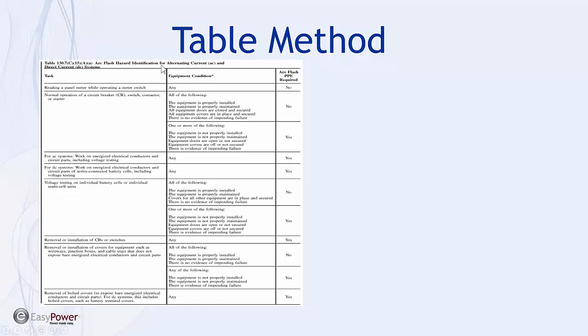When we talk about the table method in 2015 for determining PPE required for arc flash safety, the descriptions start with a series of tables that give a go/no-go on whether PPE is required. As you get into more detail where it is required, they give a series of questions on how to determine that. This is significant because, at least in this first category, they tell us quite specifically where we don't have to put on PPE. During normal operation of a circuit breaker, switch, or contactor, if we can answer all of five questions positively, then we don't need to put on PPE. These are very important questions.